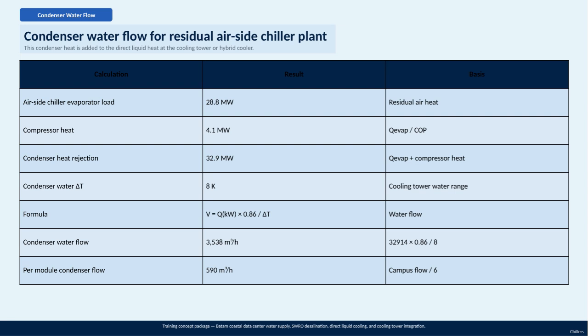This flow is then divided by 6 modules on the campus, resulting in around 590 cubic meters per hour per module. This breakdown helps to optimize the water flow requirements for maintaining efficient cooling tower and chiller operation within the Batam Coastal Data Center's integrated system.